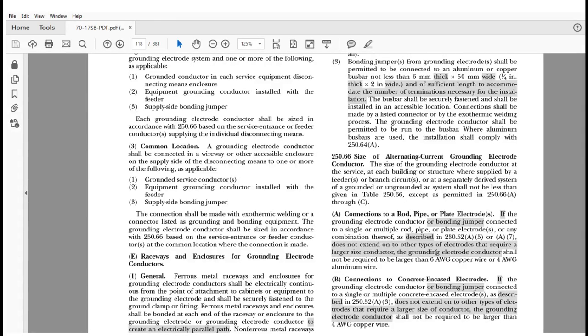So as you see here, it says the words or bonding jumper, which is to make it clear that you can connect multiple rods, pipe, or whatever together, and it is still not required to be any larger than it states right here, a 6 copper. Keep in mind that most of these electrodes on tests can't handle any more than that. A 6 to a rod, 6 to a plate, 6 to a pipe doesn't need to be any larger. Now, I have seen engineers, bless their hearts, size something as large as a 4/0 copper, even a 500 kcmil, to a ground rod, and have no real explanation of why they're doing it.